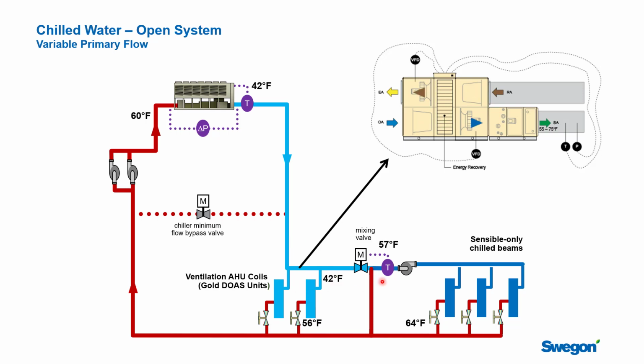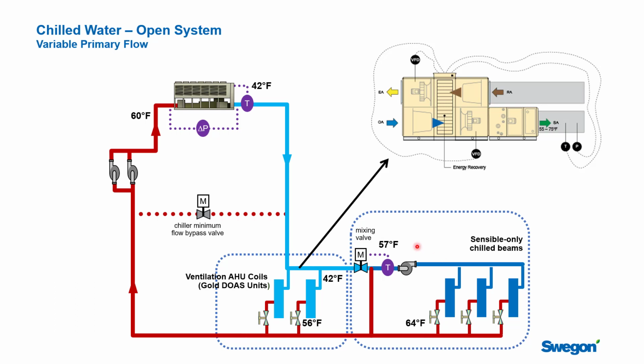Now, chilled beams themselves are dry devices, which means the chilled water that's sent out to those beams has to be above the dew point of the space. And typically the design condition is 57 or 58 degrees Fahrenheit. So you can see that there is a second loop over here that is looking at the chilled water that's flowing out to the chilled beams. These here will be the chilled beams. There's their flow control valves, and this water is coming in at 57 degrees and going out at 64. And at a high level, you can see that the air handling units are on a primary loop, and then there's a secondary loop here that is servicing the chilled beams themselves.